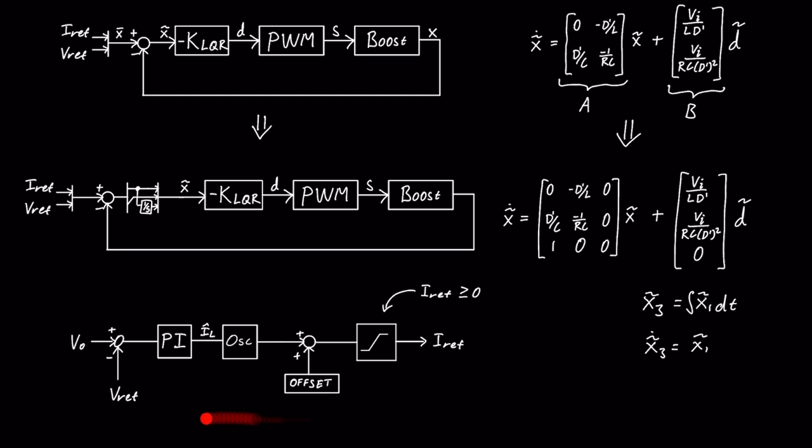This PI controller works by finding a peak value of the current, and then you oscillate it if you want a certain waveform. For example, for a PFC, you will have a sinusoidal waveform, and you may also want to add some offset. But I think in most cases, you don't need an oscillator and you don't need an offset. You just need a limiter because the current can't be lower than 0. And maybe you also want some anti-windup as well. So you can just add some anti-windup.